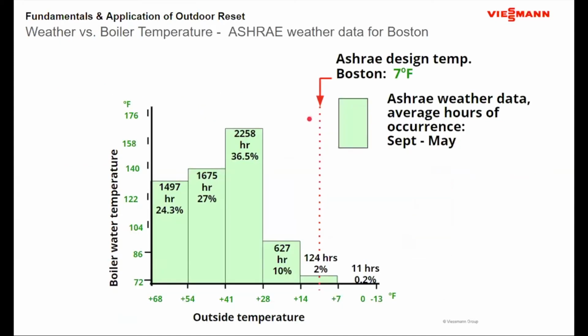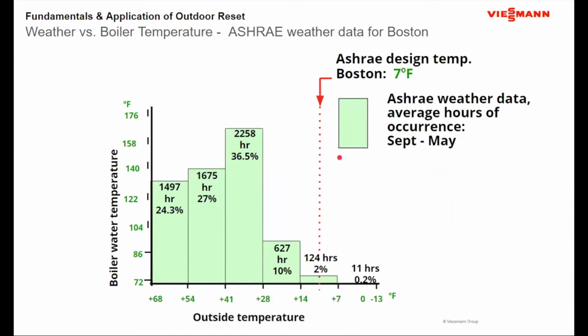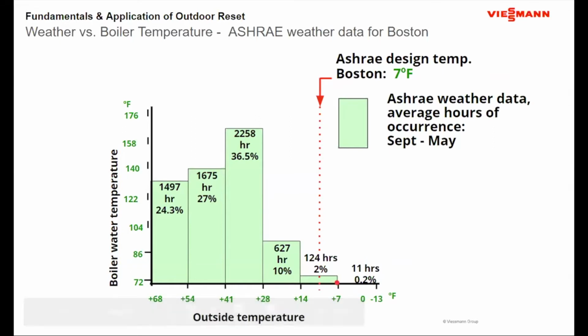Okay. Now, the thing we start to look at these kind of conditions is I am designing for a very specific time period. So if I was designing for 0 degrees Fahrenheit, and my chart here has been skewed a little bit from my changeover from PowerPoint to Google Slides. But if I look at this 0-degree day right here, 0-degree actually should be over here. I am designing for a condition that, if I look at a spread from about 7 degrees Fahrenheit to 0 and 0 to -13, I'm designing for a little bit more than 2% of the heating season.